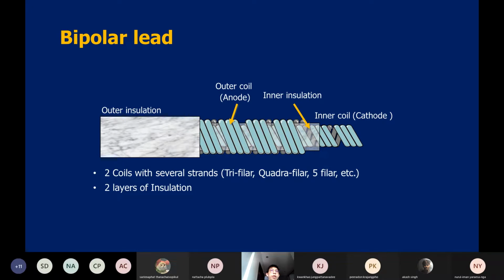I mean that you still have to connect the lead to the pulse generator, that is the thing you need to do. But you can generate the electrical impulse from the tip of the lead itself. The pulse generator does not need to be the anode of the system. And if the outer layer, the anode of this type of lead, breaks down or some problem occurs, you can still use it as a unipolar. You can switch off this outer layer and turn it into unipolar by using the pulse generator as an anode.